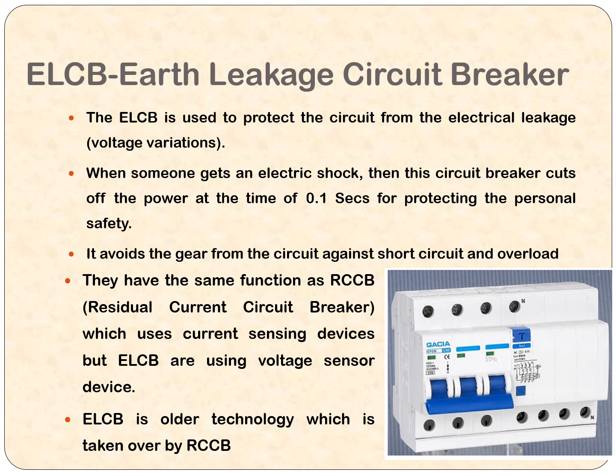So another thing is emerging, which is called the residual current circuit breaker, RCCB. Residual current means, after loading your external load, if your ground has an elevated voltage due to earth leakage, that is, your earth rod is not properly grounded, that voltage can induce a current in your body. So that is predicted and rectified, that is, corrective actions may be taken by this RCCB by measuring currents, not voltage as ELCB does. So ELCB has now been replaced by RCCB in new technology.